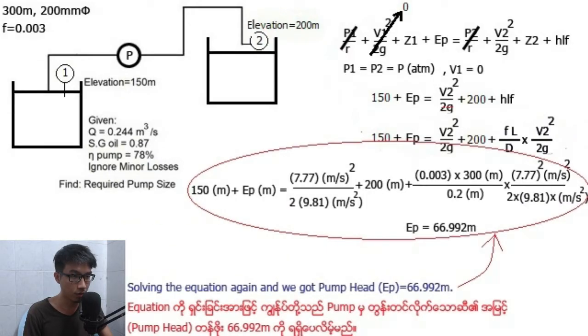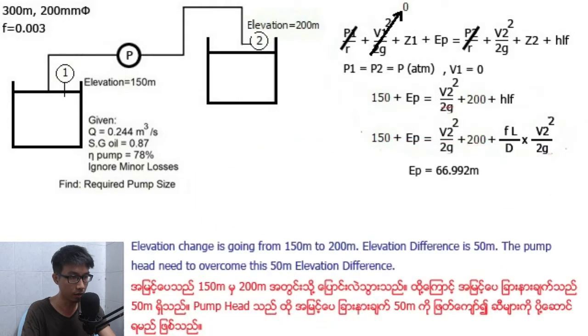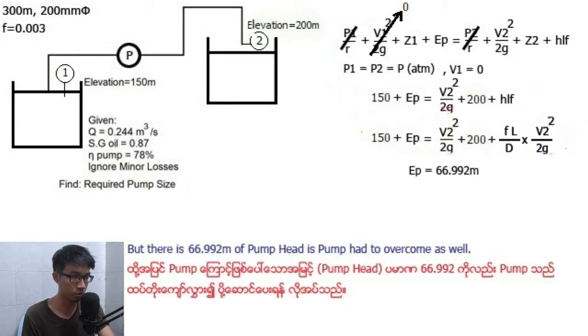Gravity g is 9.81 meters per second squared. Solving the equation, we got pump head Ep equal to 66.992 meters. Elevation change is going from 150 meters to 200 meters. Elevation difference is 50 meters. The pump head needs to overcome this 50 meter elevation difference, but there is 66.992 meters of pump head needed to overcome head loss as well.